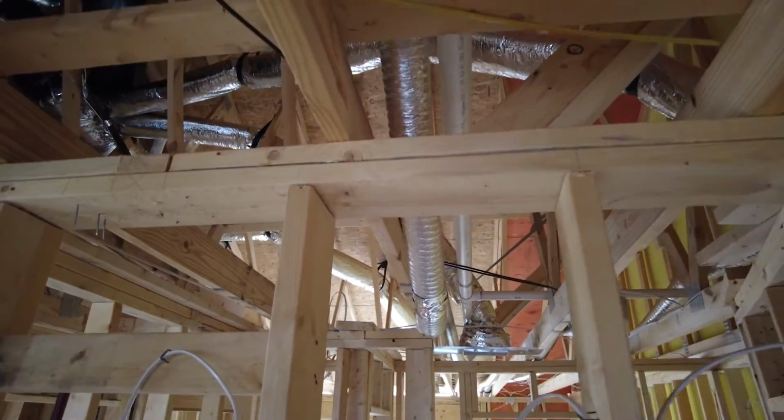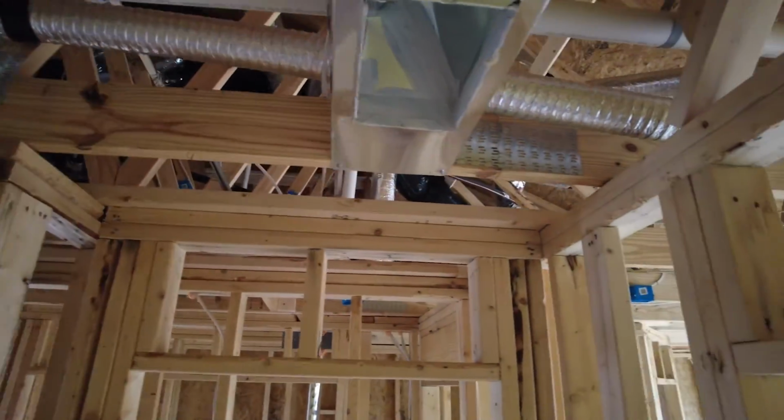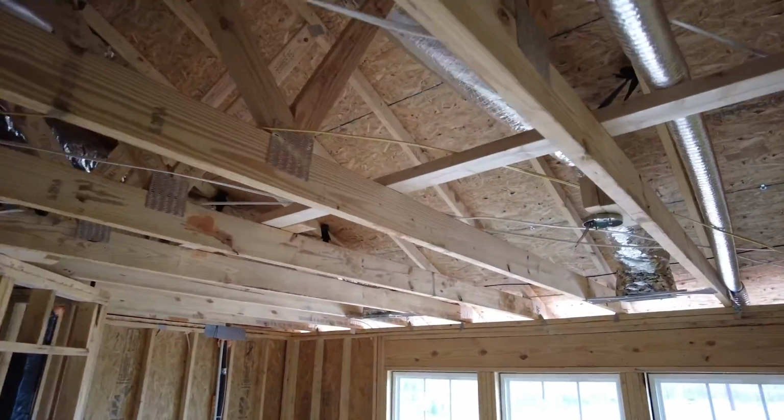Then the last problem with this bath fan is that that flex duct runs over 30 feet in distance. So they're running the bath fan from this bathroom all the way to the back of the building 30 feet, when just turning it 90 degrees could cut that distance in half and run it perpendicular out the side of the building. So 4 problems with the bath fan on this particular project that we commonly see when we walk through new construction that meets code but doesn't embrace the latest best practices of high performance building.